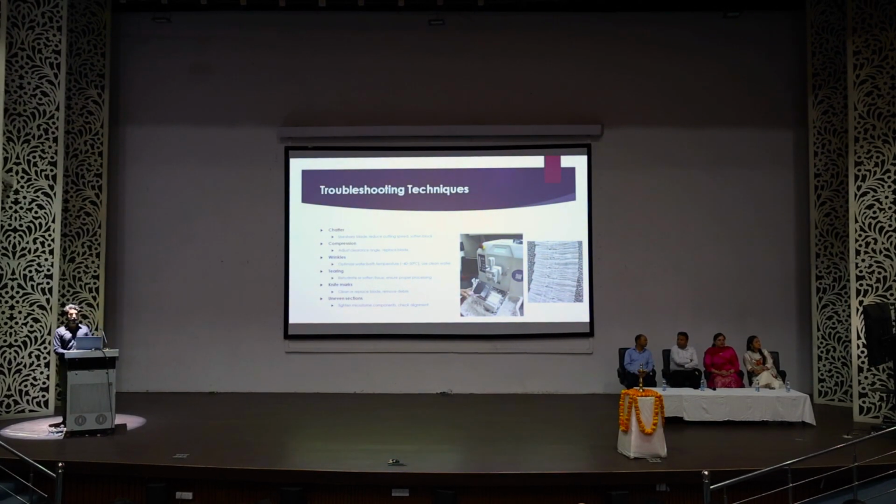How to troubleshoot these problems which we are facing in microtomy? For chatter, use a fresh blade, slow speed of sectioning, and soften the block by increasing its temperature. If the block is hard because of cooling, or hard because of calcification, then, as Fayaz already said, we have to go for decalcification. He already mentioned it. For compression, adjust the clearance angle and replace the blade.